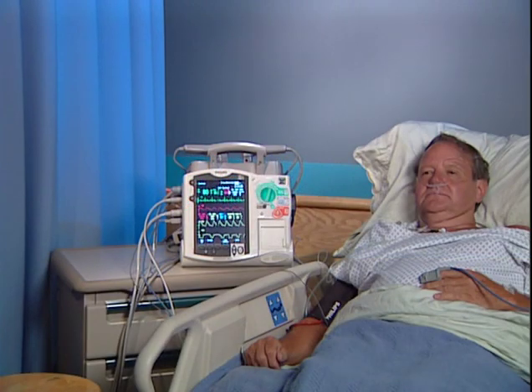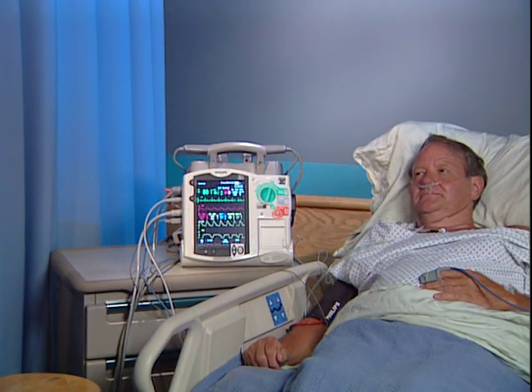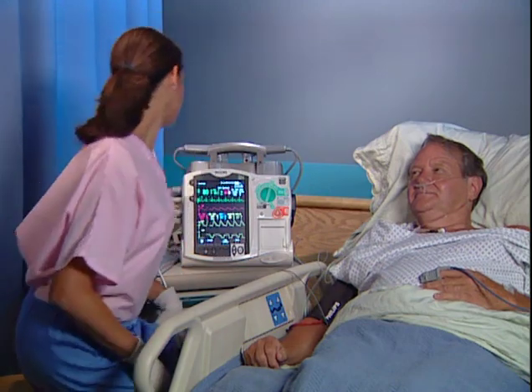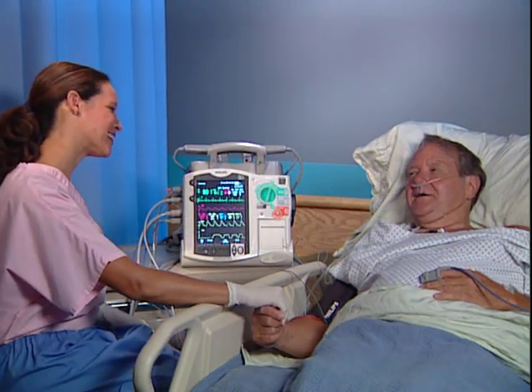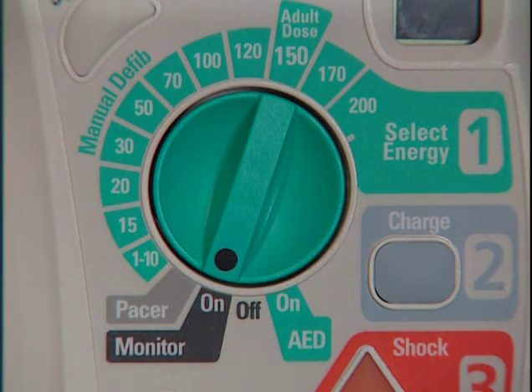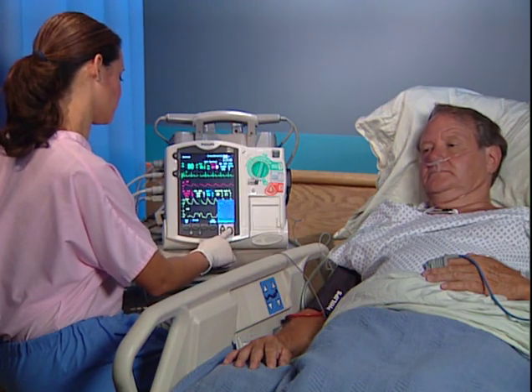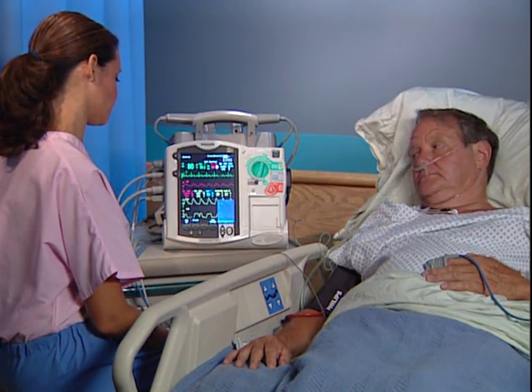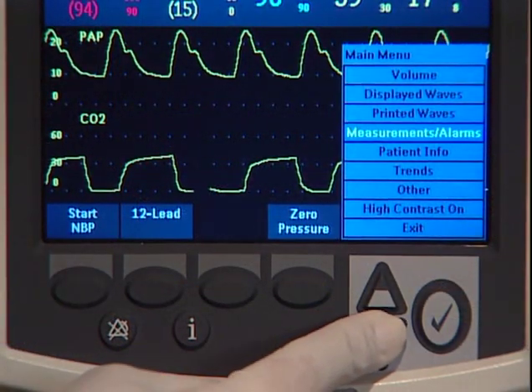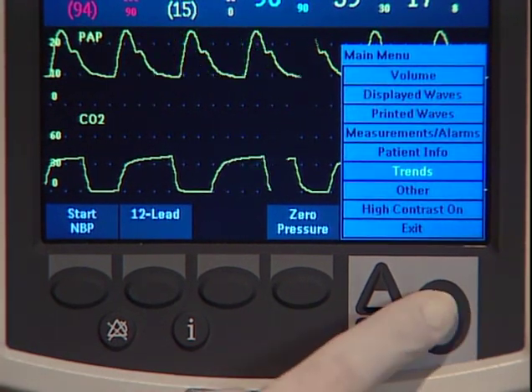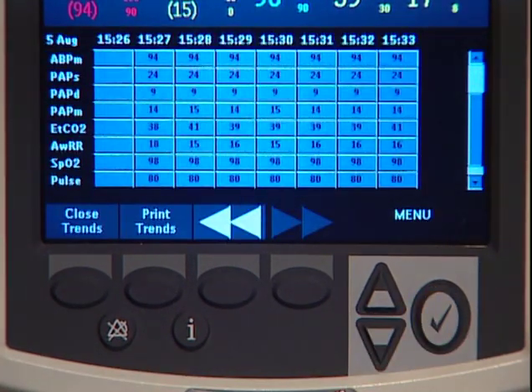The HeartStart MRX can store up to 12 hours of vital signs trending data for review, printing, or transmission. To view the stored trending data, the HeartStart MRX must be in monitor mode. Press the Menu Select button. Navigate to Trends and press the Menu Select button. The trending report displays here.